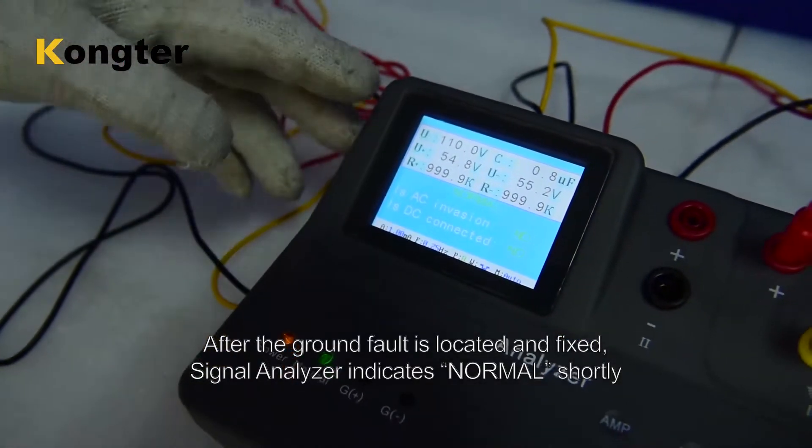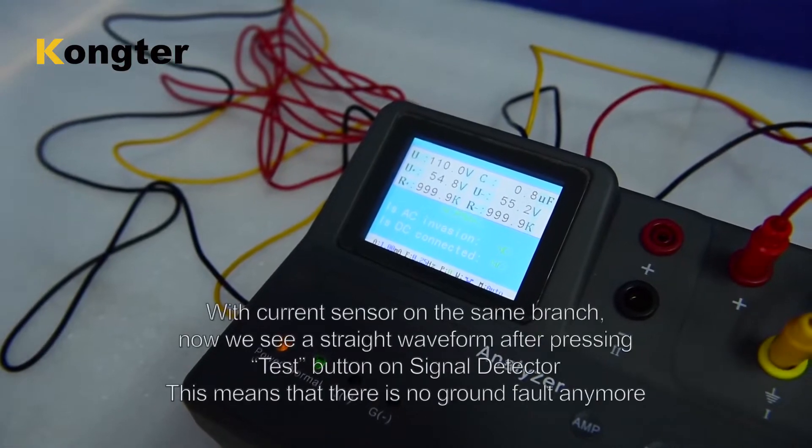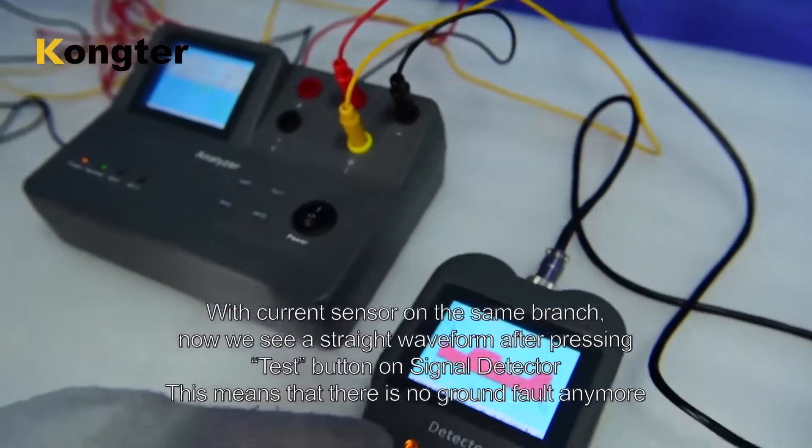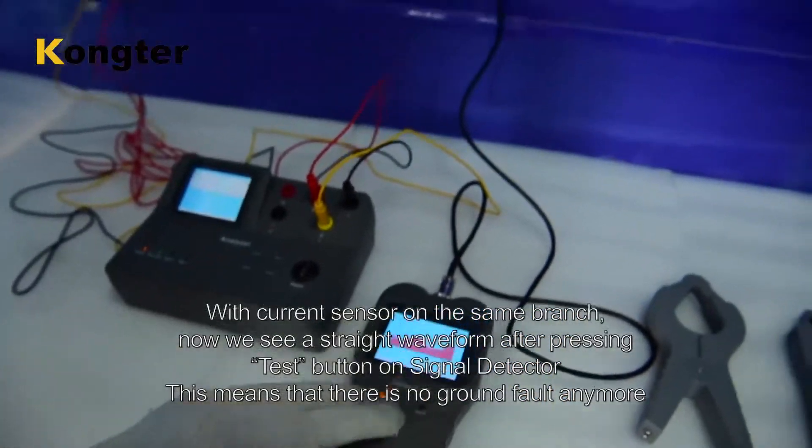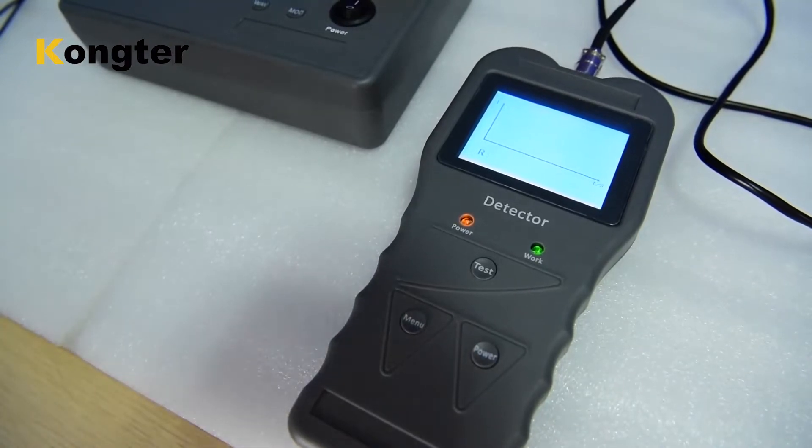After the ground fault is located and fixed, signal analyzer indicates normal shortly. With current sensor on the same branch, now we see a straight waveform after pressing test button on signal detector. This means that there is no ground fault anymore.